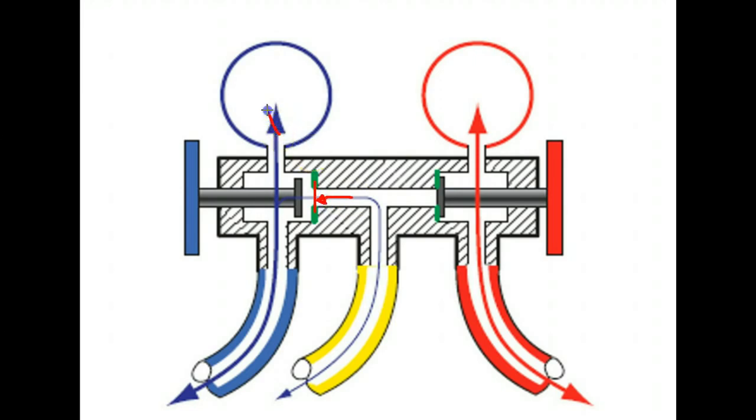And you'll see this pressure, the low side pressure come back down and stabilize. You're going to want to let this stabilize for 10 or 15 minutes. If you don't, you're going to be in trouble. So charging a system takes time if you do it right. What you'll do is you're going to allow refrigerant to enter, close the valve back down, let the system pressures stabilize. Then you're going to let the system temperatures stabilize. And you'll do this over and over again until you hit the proper measurements according to the manufacturer.